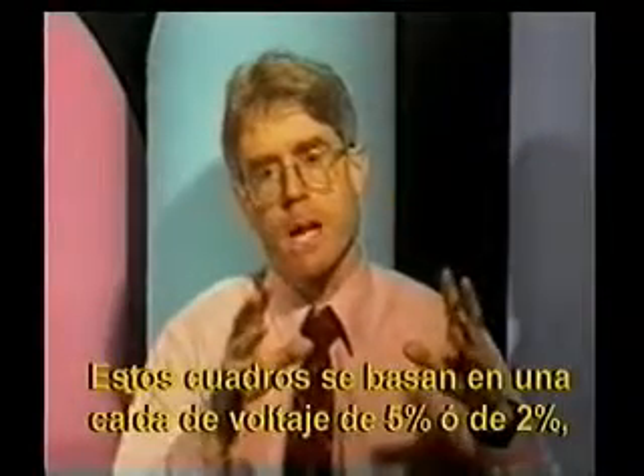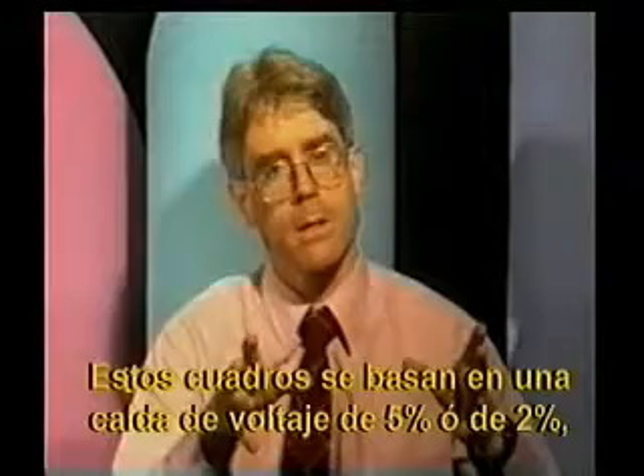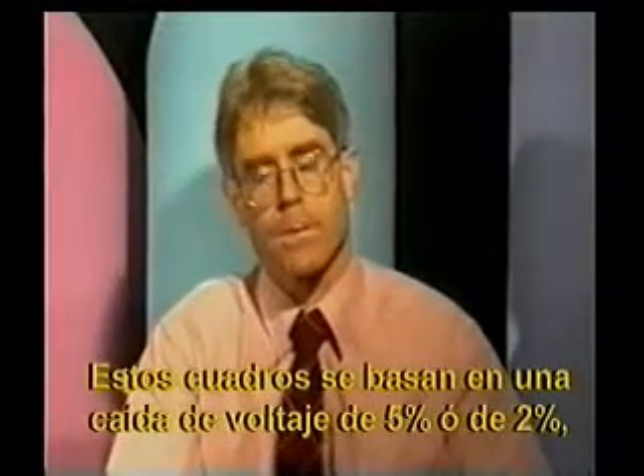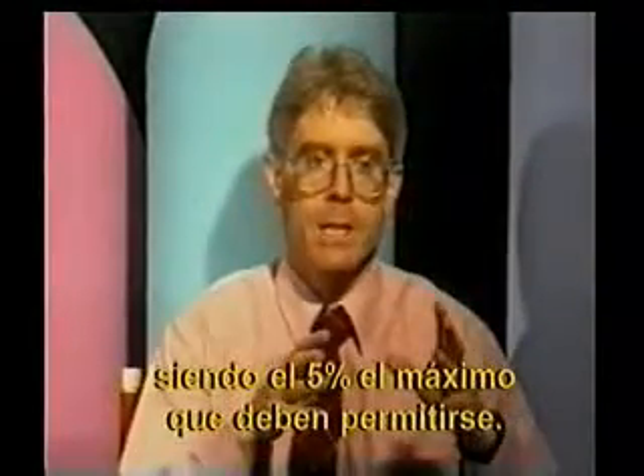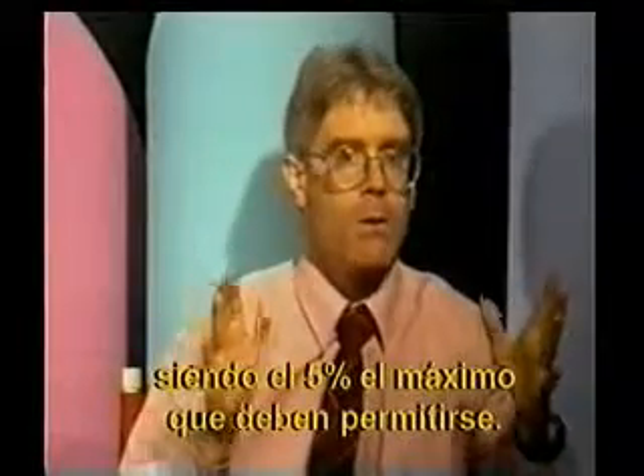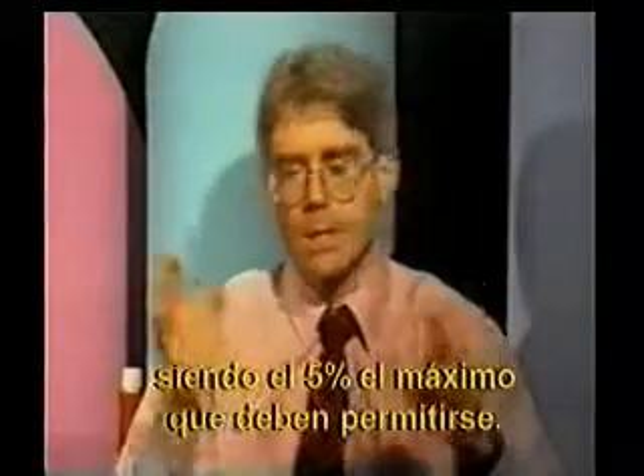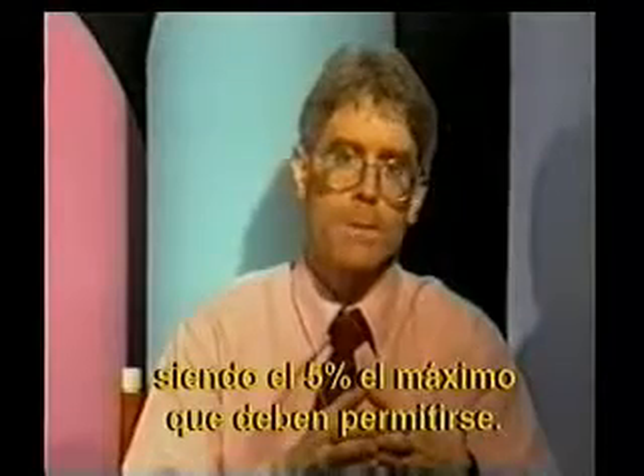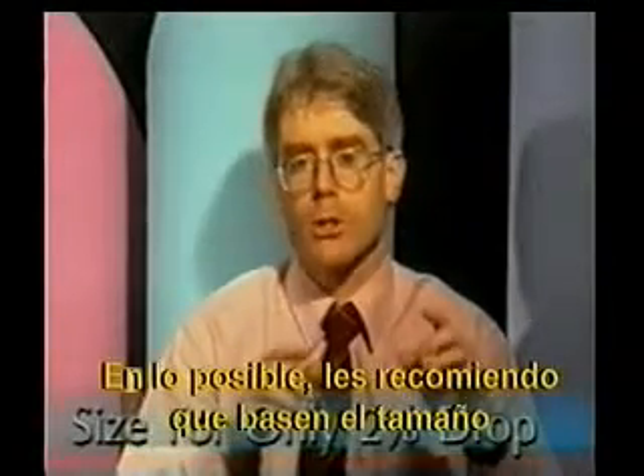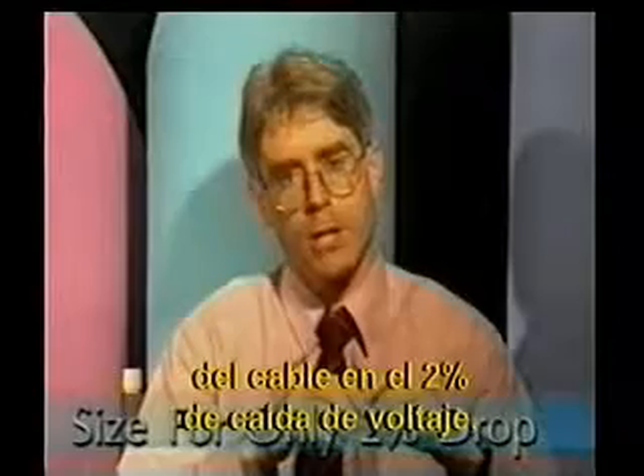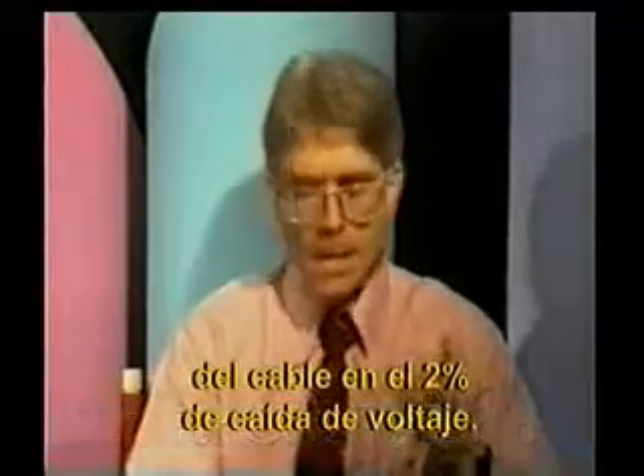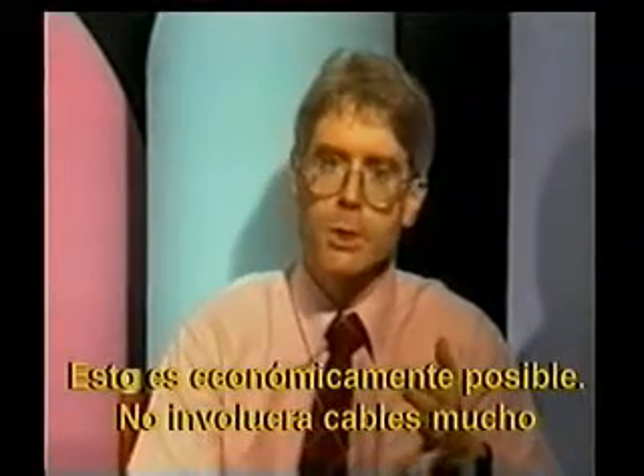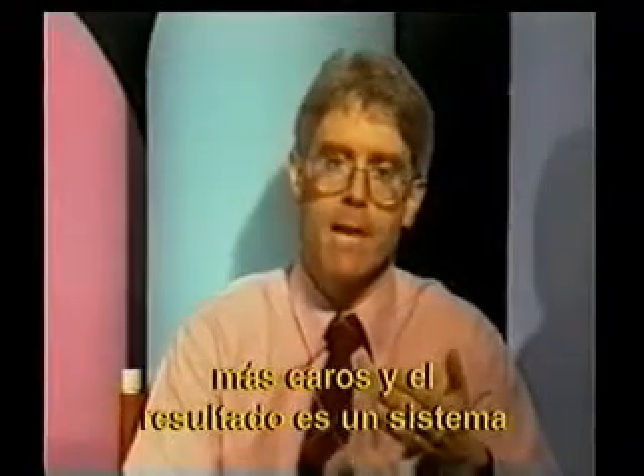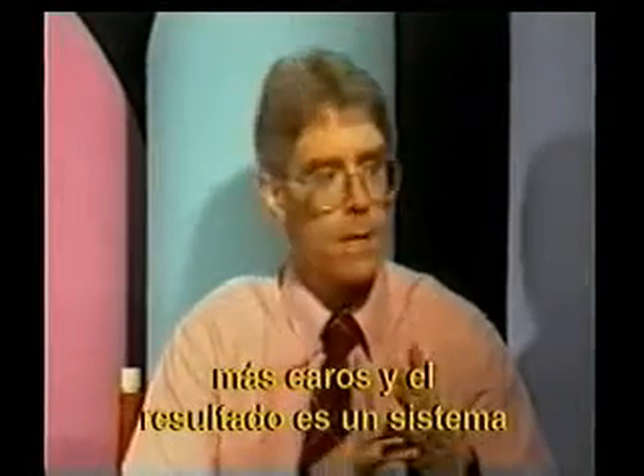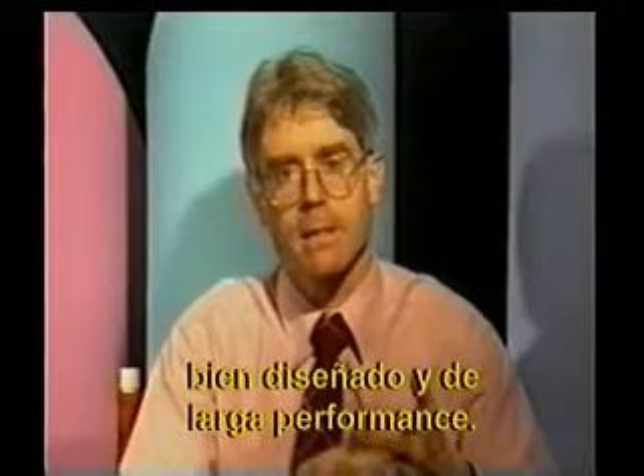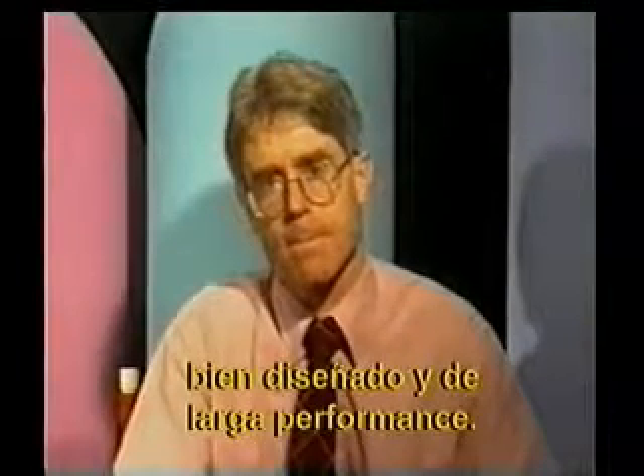These charts have been designed around a 5% drop or a 2% voltage drop. The 5% drop should be considered really the maximum allowed that you should ever consider between your array and your battery, or your battery and your load. If at all possible, you should size your wires based on only 2% drop. This is economically possible. It doesn't involve choosing wires that are that much more expensive, and it leads to a much more appropriately designed and long-performing system.